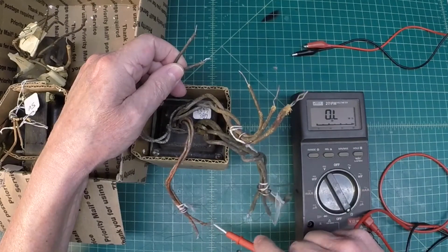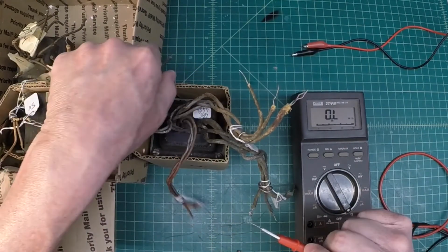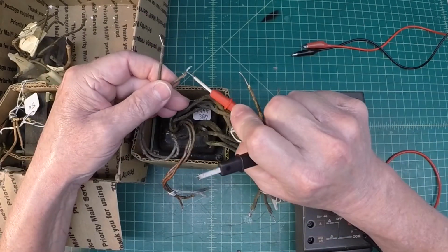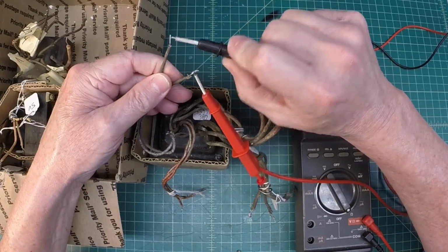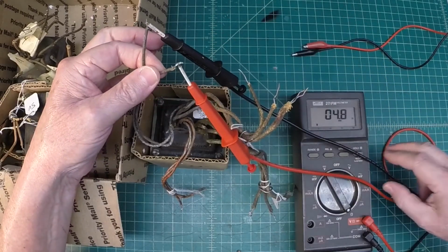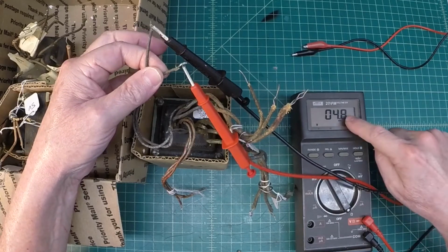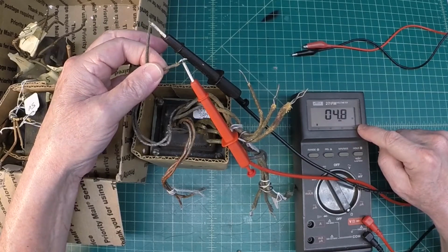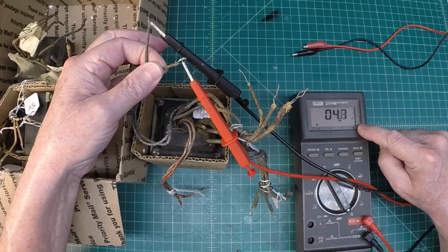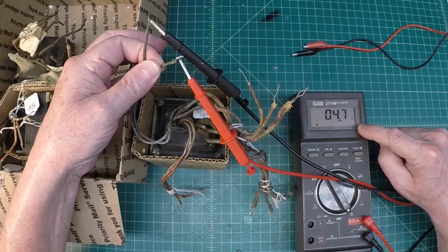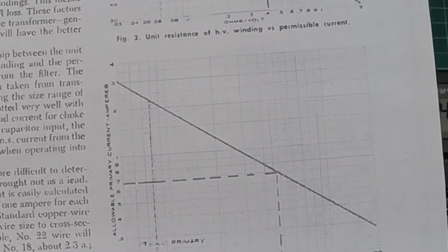Let's move the meter leads now from the high voltage back over to the primary input and read the DC resistance here of the primary windings, and you can see I have 4.8 ohms of DC resistance. Let me make a note of that. Back to the meter here, you can see we read 4.7 to 4.8.